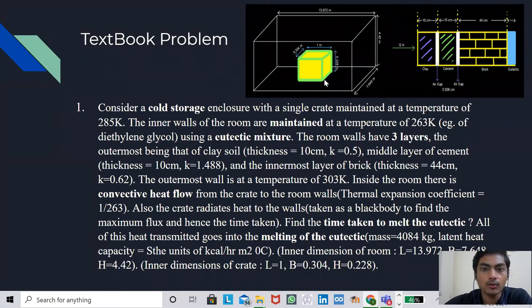As we have discussed our control volume ecosystem, now we can frame our problem statement. There is a cold storage enclosure with a single crate maintained at a temperature of 285 Kelvin. The inner walls of the room are maintained at a temperature of 263 Kelvin with the help of eutectic mixture. The room walls have three layers: the outermost is clay soil, the middle one is cement, and the third one, the innermost layer is bricks. The outermost wall is at a temperature of 303 Kelvin. Inside the room, there is a convective heat flow from the crate to the room walls and the thermal expansion coefficient for the same is 1 by 263. Also, the crate radiates heat to the walls and the crates are assumed to be as a black body so that we can find the maximum heat flux. Now we will find the time taken to melt the eutectic. All the heat transmitted is going to melt the eutectic and with the mass, the latent heat capacity, the inner dimension of rooms, inner dimension of crates are given in the problem statement.